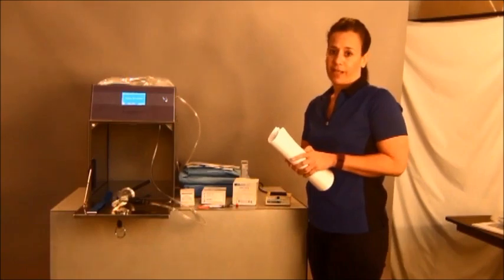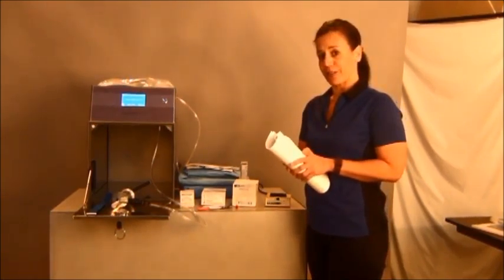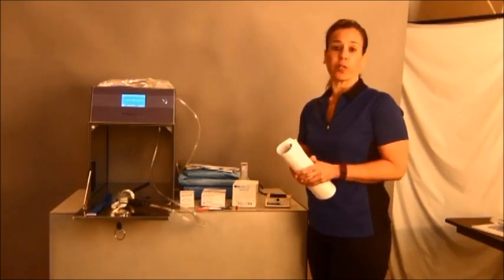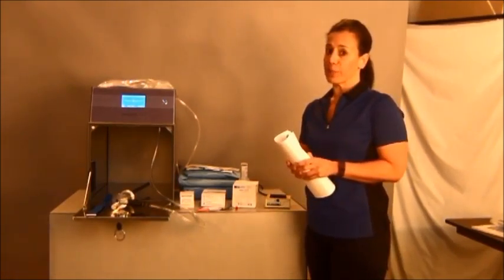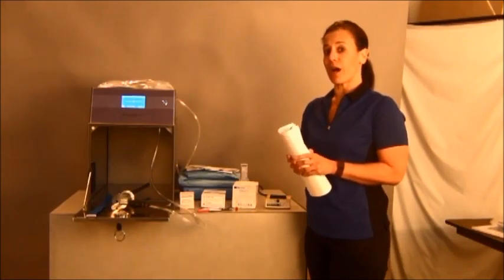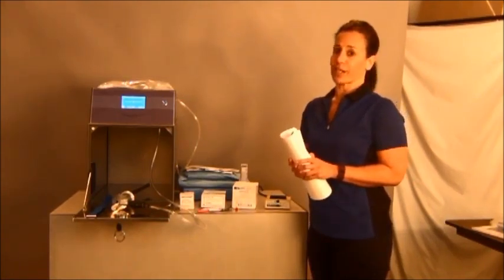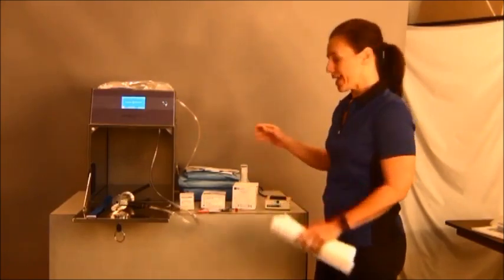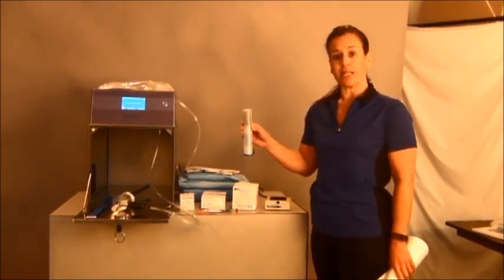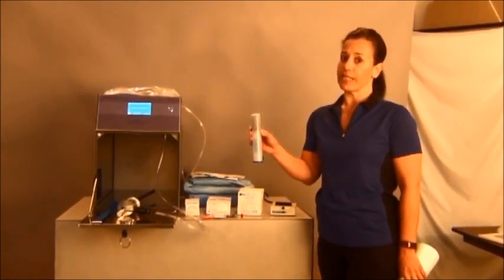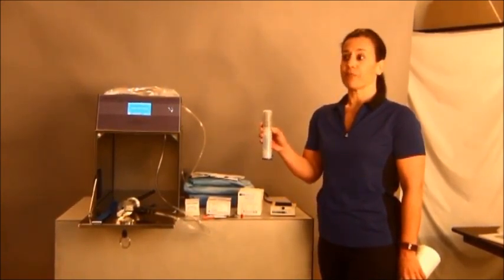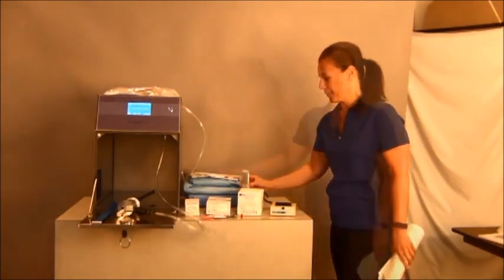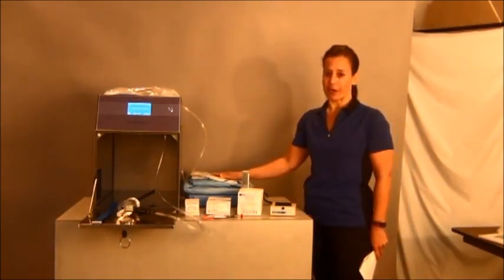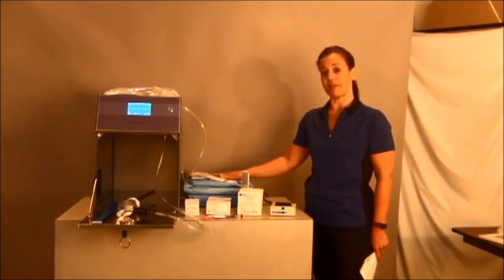The first subject I'm going to touch on is preparing for sterilization. Temperature is a very important process in storage of your gas ampules, as well as the processing of your items for sterilization, as well as the sterilization cycle. When you're storing your gas cartridges, you want to make sure that you keep these in a cool area below 70 degrees that is devoid of sunlight. When preparing your items, you want to make sure that the area in which these items are prepared is at least 30% humidity, as well as 65 to 85 degrees.